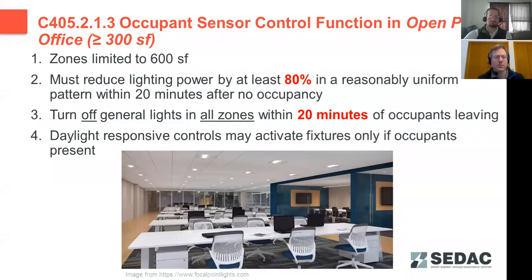Next, moving over to open plan offices. This has specific requirements, such as zone size limits of 600 square feet. Then these next two requirements go hand in glove here. The first is that we have to reduce the lighting power by at least 80%, whereas for warehouses it was 50%. Here it's at least 80% for any particular zone when that zone no longer is detecting occupancy after 20 minutes.